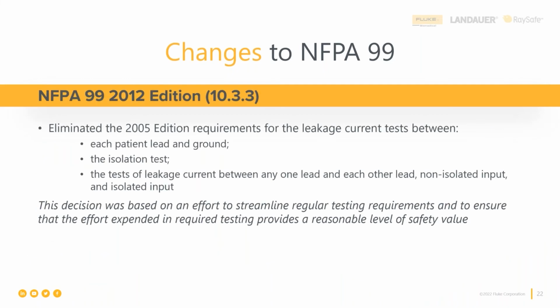All right, the 2012 edition of NFPA 99 eliminated the requirements for leakage current tests between each patient lead and ground, the lead isolation test, that's mains on applied parts, and the test of leakage current between one lead and all the other leads, non-isolated and isolated. So this decision was based on the effort to streamline regular testing requirements and ensure that the effort required provides a reasonable level of safety when it comes to what? Causes of electrical fire. That's what NFPA 99 cares about.